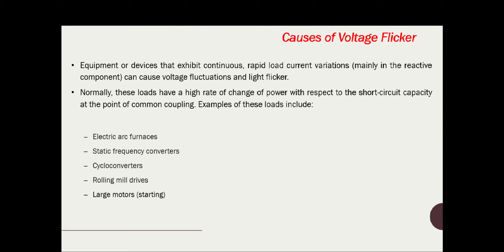Normally, such loads have a very high rate of change of power with respect to the short circuit capacity at the point of common coupling (PCC). Examples of such loads are electric arc furnaces, static frequency converters, cycloconverters, rolling mill drives, and large motors. Whenever this kind of load is present in your feeder, it will definitely cause large variation in load current, resulting in voltage fluctuation that reflects as voltage flicker in your lighting system.